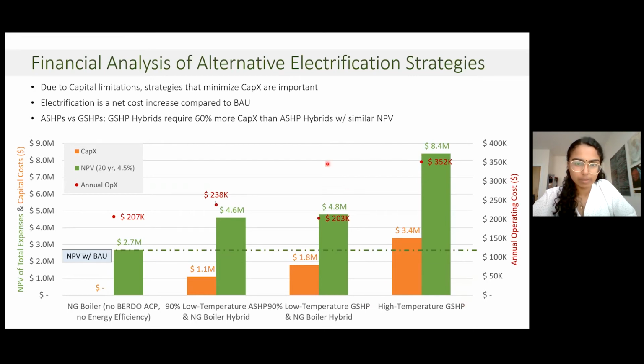When you compare these 2 heat pump systems, one is air source and the other is ground source, you notice they have a very similar net present value of total expenses. However, the ground source heat pump system requires about 60% more capital in order to implement. And this is where our capital limitations come in. The idea is, given a limited capital budget, if we can design these electrification solutions to be as little capital intensive as possible, then we can retrofit more buildings than we would otherwise, and decarbonize our portfolio quicker than we would with more expensive retrofits.